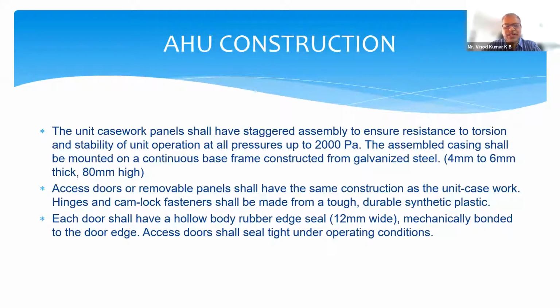Similarly, when you install the AHU close to the walls, obviously you will not have space for opening these access doors, even if the access doors are inbuilt on the AHU. So it's mandatory that when you select and design the AHUs and give them to the manufacturer, your AHU rooms should be big enough to house the AHUs, plus space for the access doors to be opened so that the technicians can go into the AHU to monitor and do maintenance.